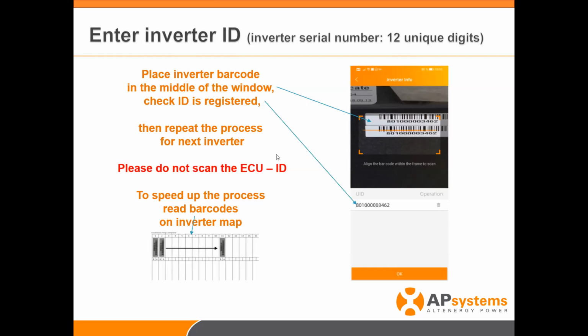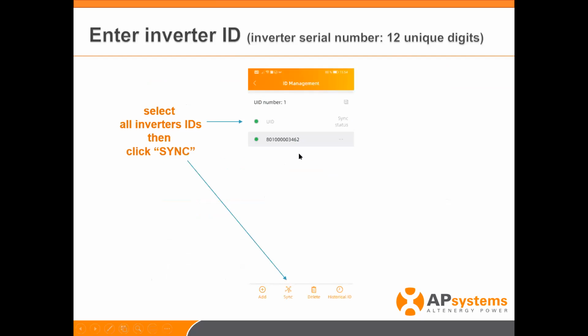Yes, absolutely. So once all inverters are properly scanned and all their IDs are showing on the list, we proceed by selecting sync to register all micros and establish the encrypted Zigbee signal. Should you have forgotten to push the sync button, the microinverters will show up on the portal but will not communicate - however, their link can be established through the EMA portal later on, so you don't have to go back on site for this.